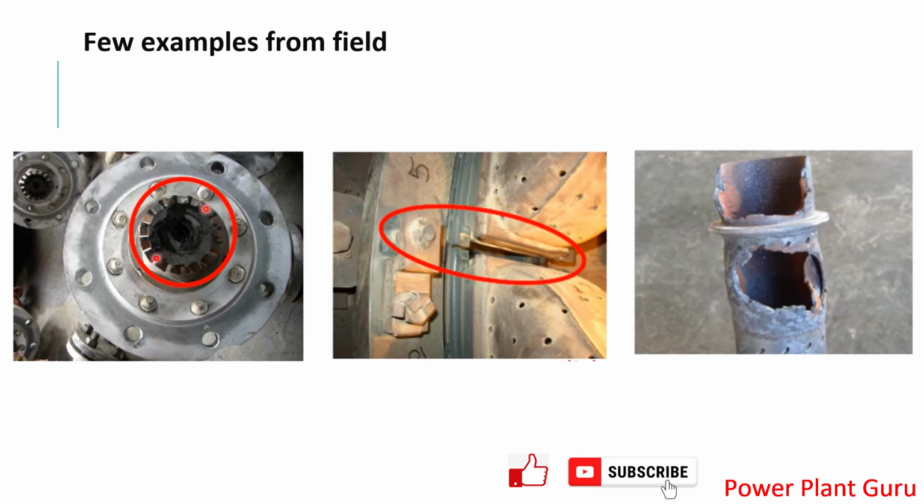If you see this particular fuel nozzle, although the picture is not very clear, what we understand is there is incomplete combustion happening at the tip, and because of that coke formation is there, which is leading to blockage of the fuel passage. Once you try to re-inject the liquid fuel, you will see that the flow is not coming from this nozzle. That means this nozzle is cold compared with all other circumferential nozzles. That means this turbine has a spread issue.